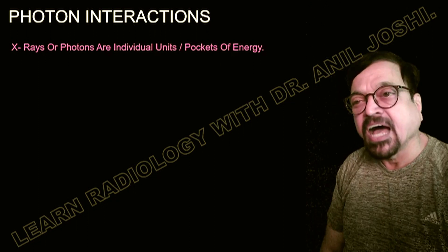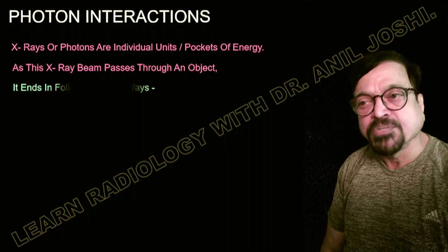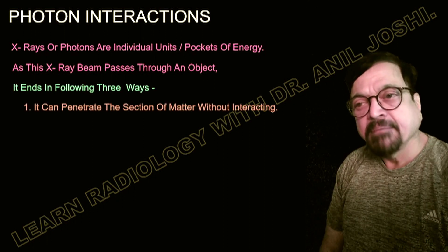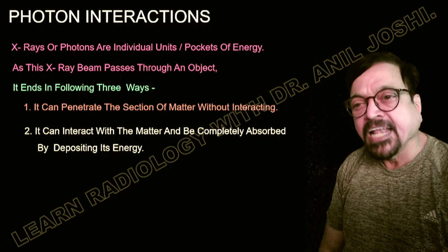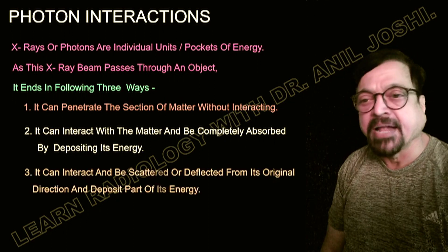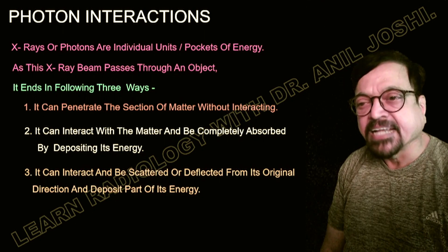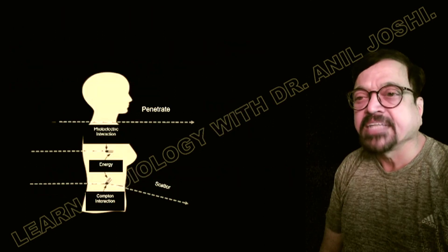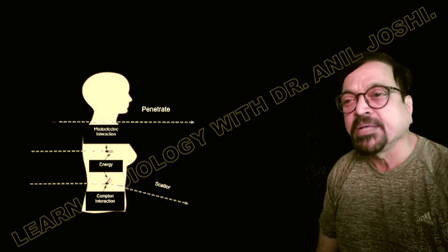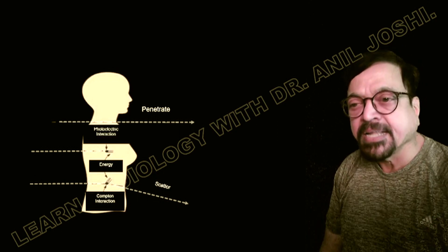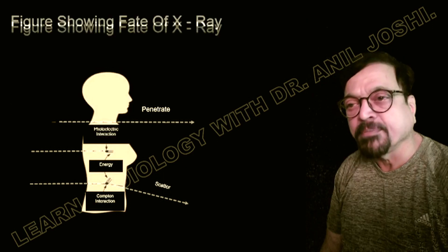X-rays or photons are individual units or packets of energy. As an x-ray beam passes through any object, it ends in one of three ways: it can penetrate the section of matter straight through without any interaction; it can interact with the matter and be completely absorbed by depositing its energy; or it can interact and be scattered or deflected from its original direction, depositing part of its energy. These three outcomes — total absorption, transmission, or partial absorption — all contribute to image formation.